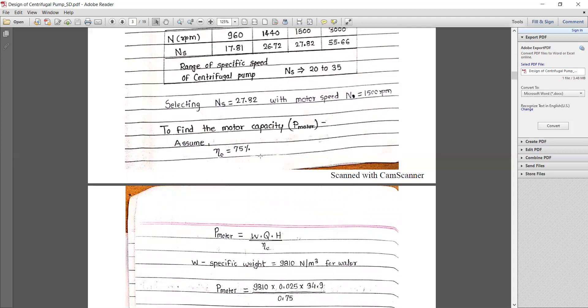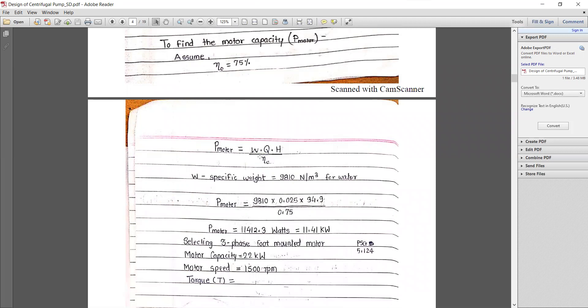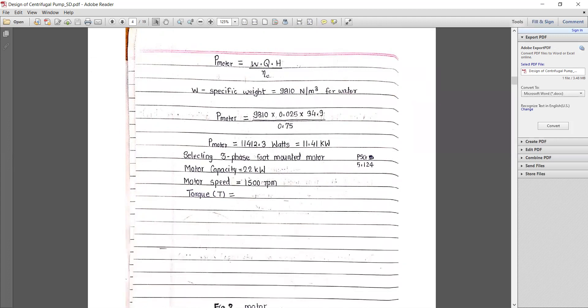Now we find the motor capacity, considering 75% overall efficiency. Motor power P = (w × Q × H) / η, where w is the specific weight of water = 9810 N/m³. Using the manometric head Hm, we get P = 11,412.3 W = 11.41 kW. Referring to the design data book (page 5.124), we select a three-phase foot-mounted motor; the nearest standard available capacity is 22 kW, with motor speed 1500 RPM.